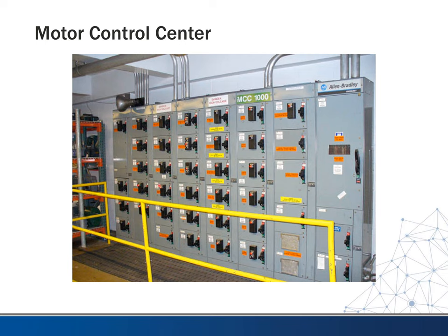And so oftentimes in industrial applications, they'll only design to the MCC and get that permitted. Then they'll come back after the building is built and signed off on, and add their connections from here out to the motor loads. One reason for that is processing loads are usually exempt from being permitted. So this simplifies the permit process.